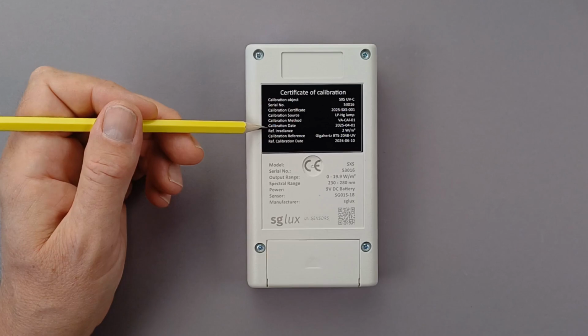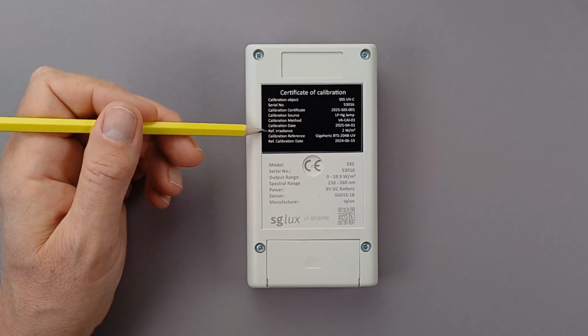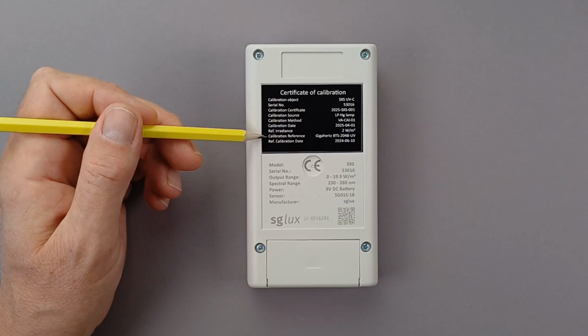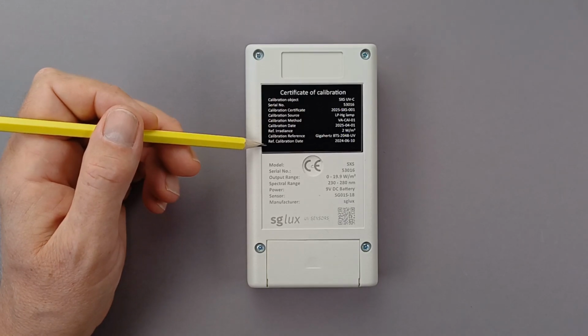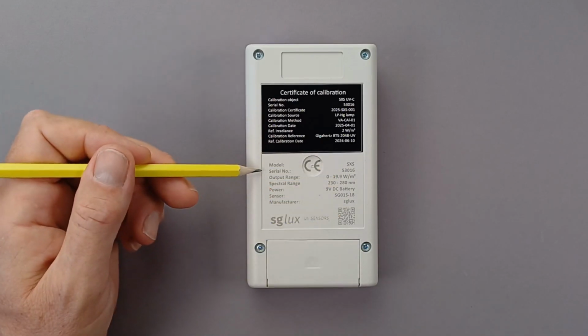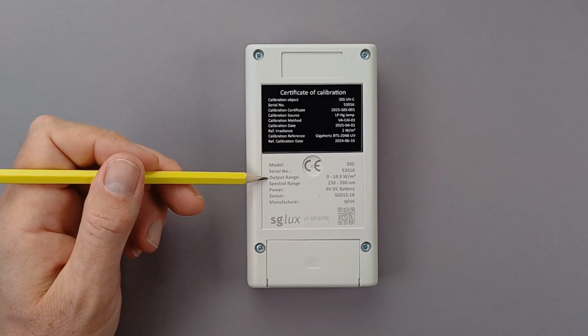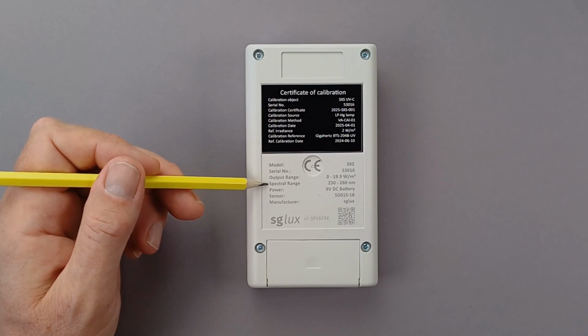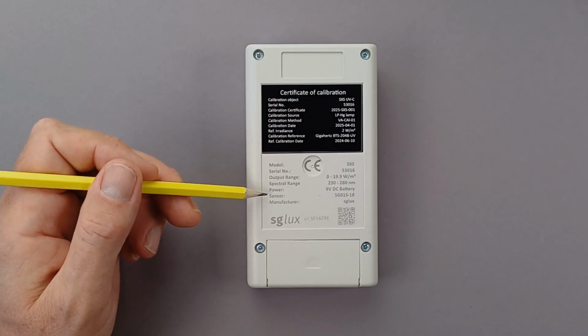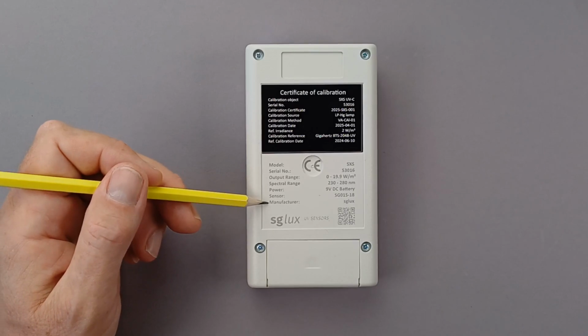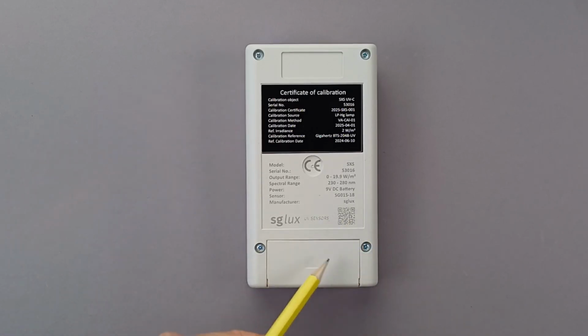The device should be recalibrated in our laboratory annually, or at least every 2 years. Below this is the calibration reference traceable to national standards, in this case a spectroradiometer from the manufacturer Gigahertz Optic, and the calibration date of this reference. Further information includes the model name, the maximum measurable irradiance, the measuring range of the sensor used, the power supply, the sensor used and the manufacturer, as well as a link to the device data sheet.